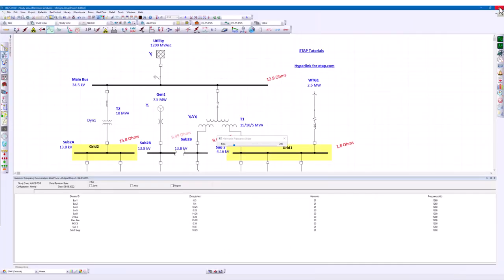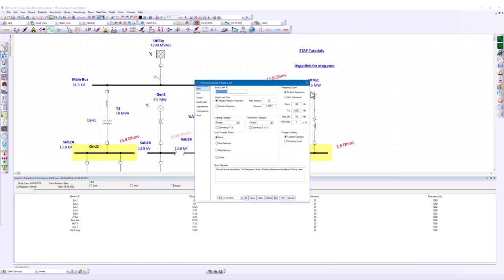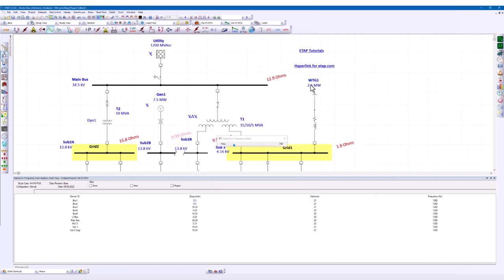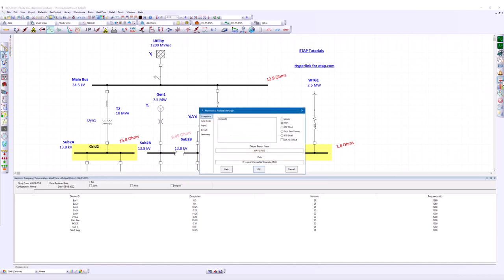One enhancement we did for frequency scan can be seen from the study case. Now we support the frequency scan based on positive sequence and zero sequence impedance. The calculation would be done based on the option here. The tabulated results can be seen from the frequency scan report manager as well.